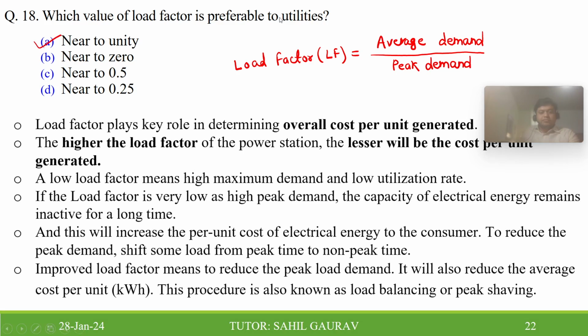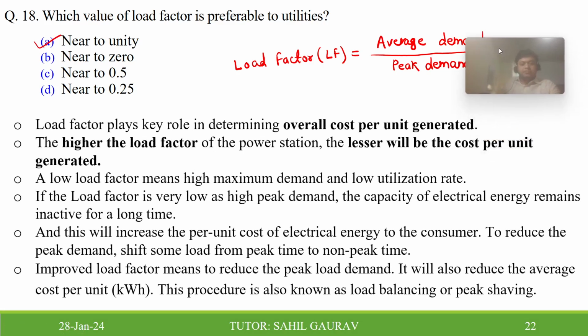And the reason behind this is what I have mentioned in the points here. The load factor plays a key role in determining the overall cost per unit generated. So the higher the load factor of a power station, the lesser the cost per unit generated. And vice versa, a lower load factor means high maximum demand and low utilization rate. So if the load factor is very low, with high peak demand, the capacity of electrical energy remains inactive for a longer time, and this will increase the per unit cost of the electrical energy to the consumer.